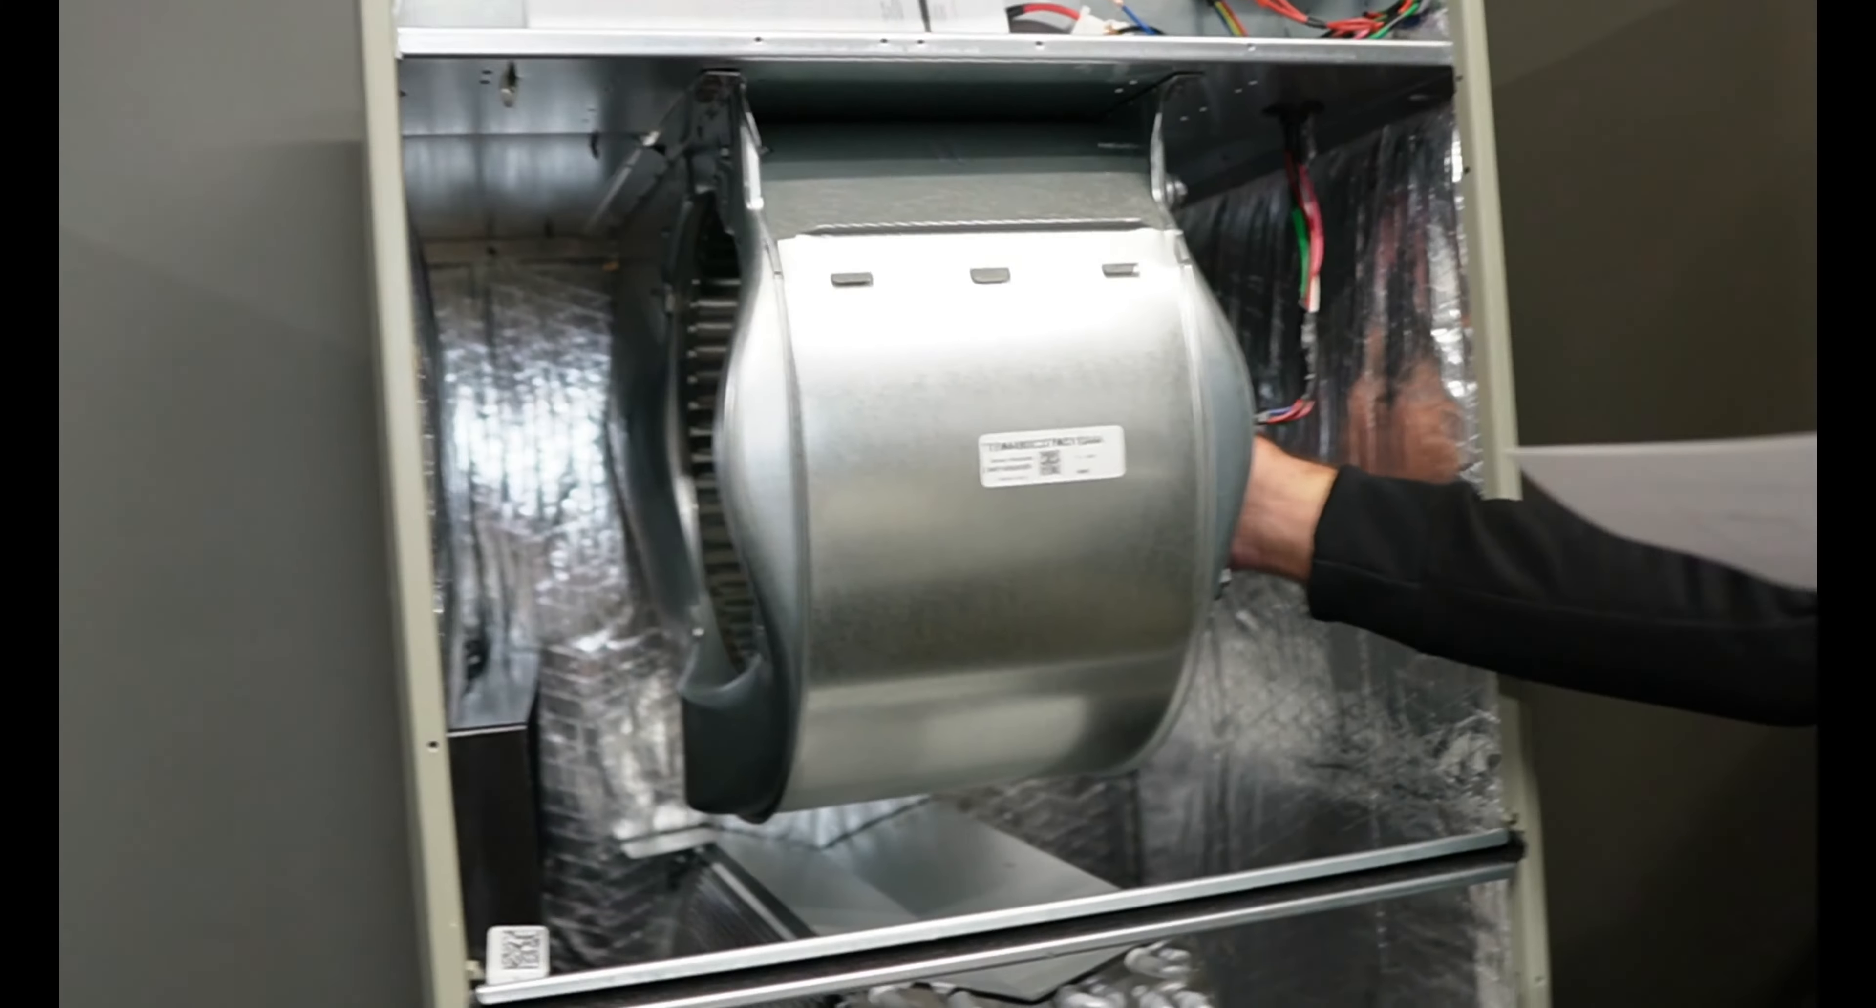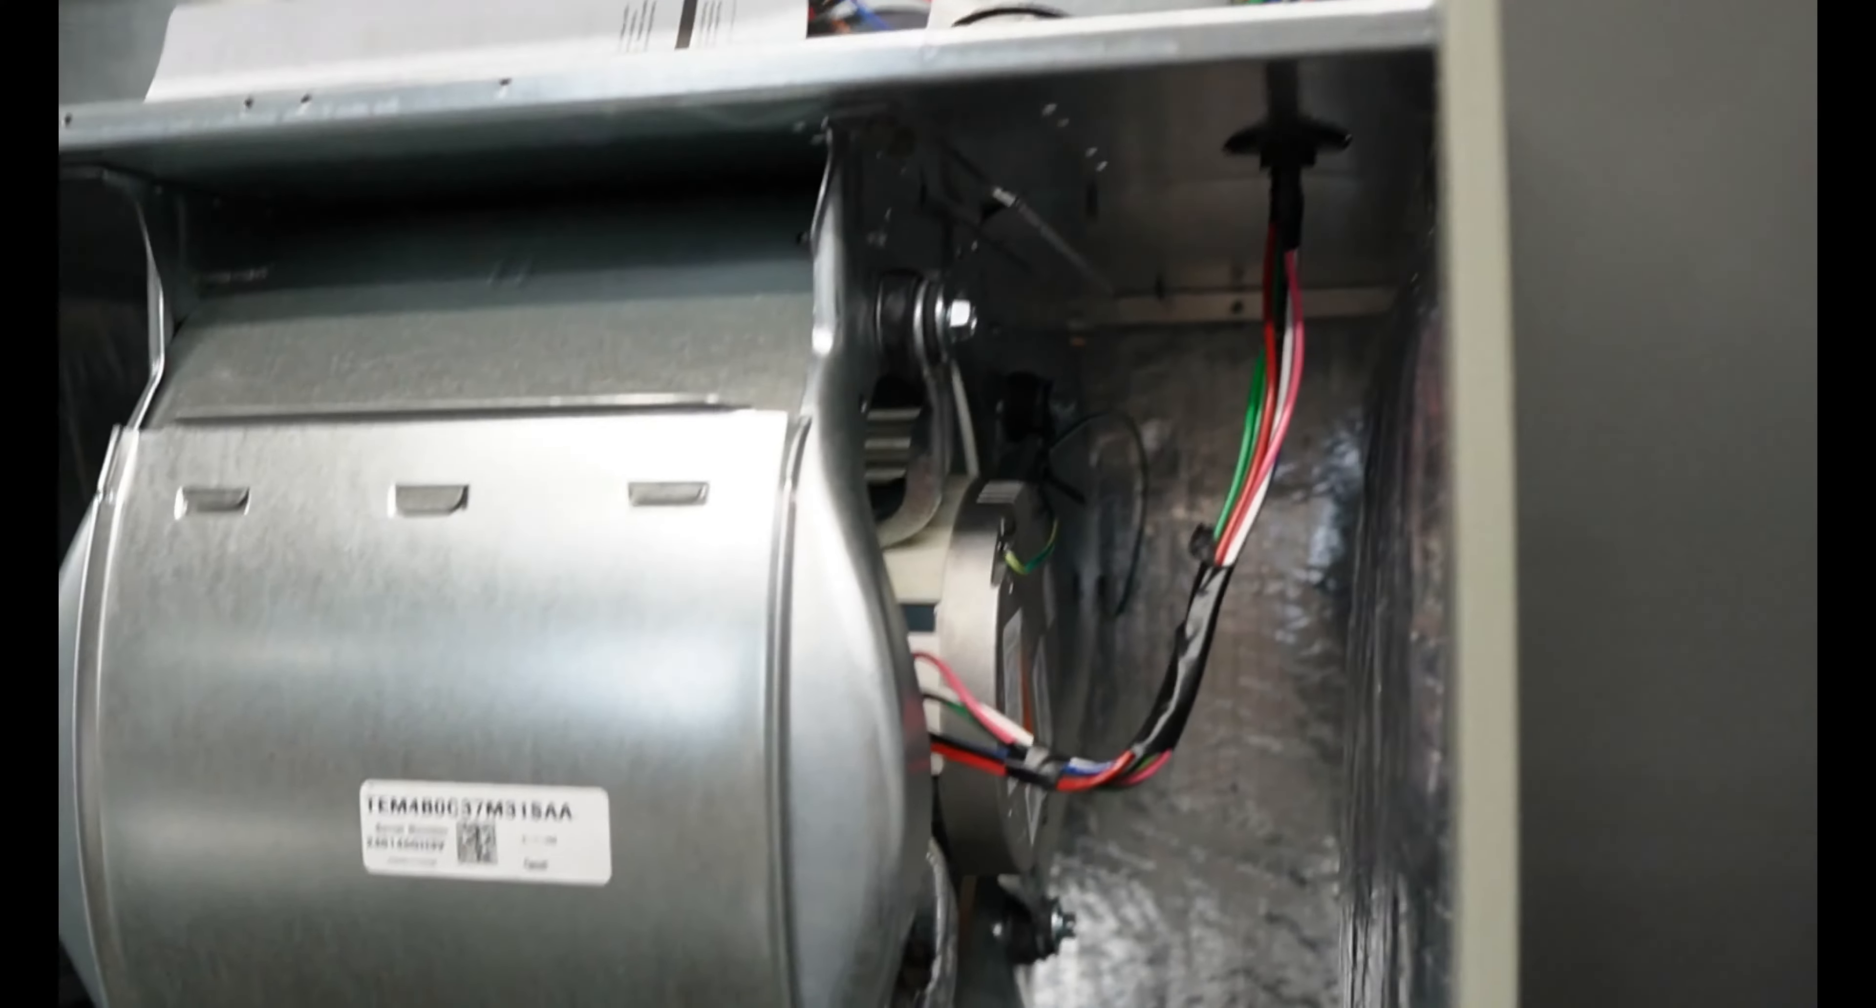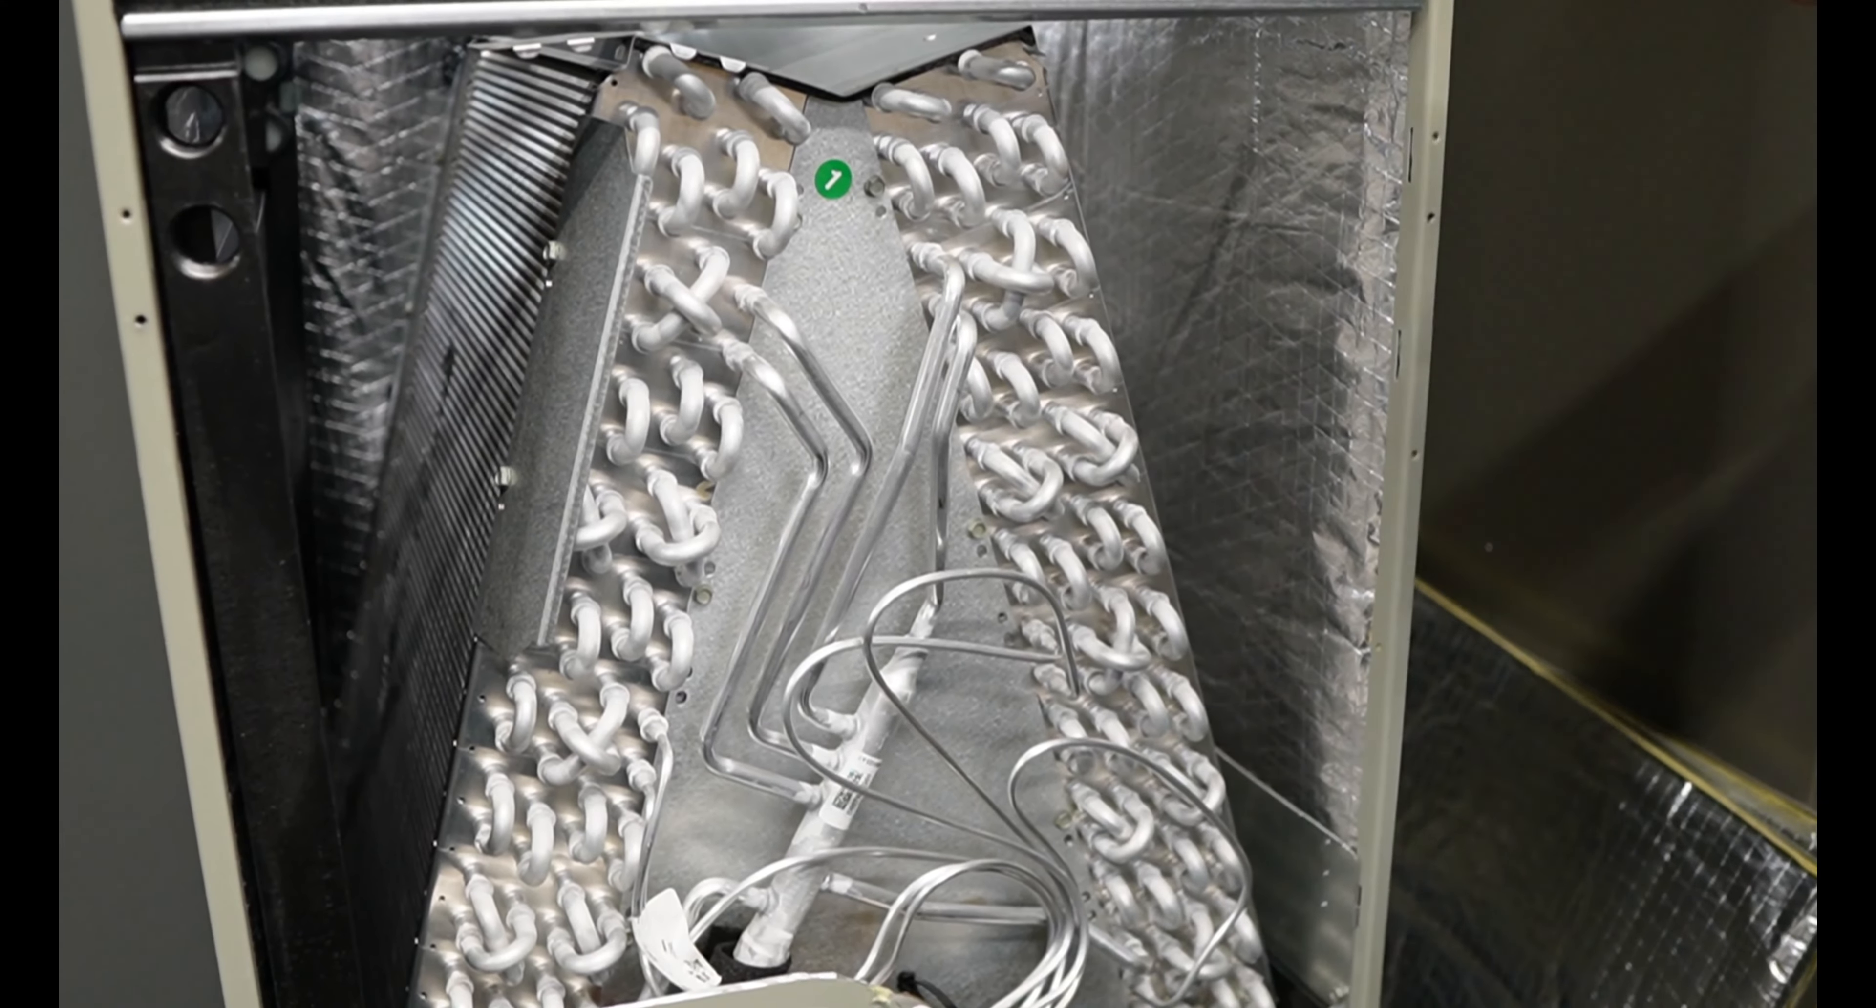It has four motor mounts on here. Going to give it 10 points for that. Very good. This has the Genteq 5-speed ECM motor. Famous X13 motor by Genteq. Very good motor here. Access to clean the drain pan, pretty good. 10 points for that. 10 points for the ECM. 10 points for the ECM motor.